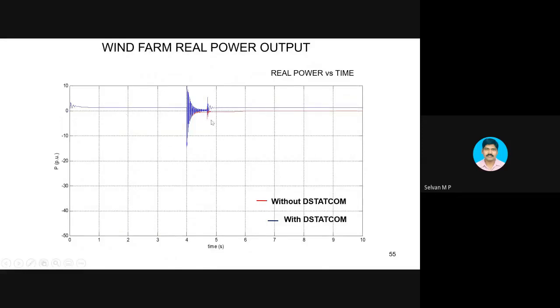So for real power, we can see the red one is without DSTATCOM, the blue one is with DSTATCOM. Before the fault, blue and red are aligning themselves, and during the fault, without DSTATCOM, the red becomes zero. It means that there is no real power output. But with STATCOM, the real power oscillates, but it gets settled. After clearing the fault, I am able to get a certain amount of real power.